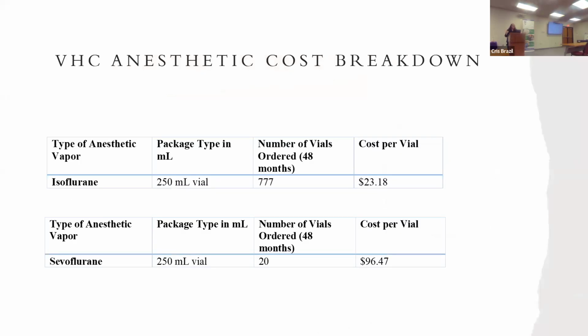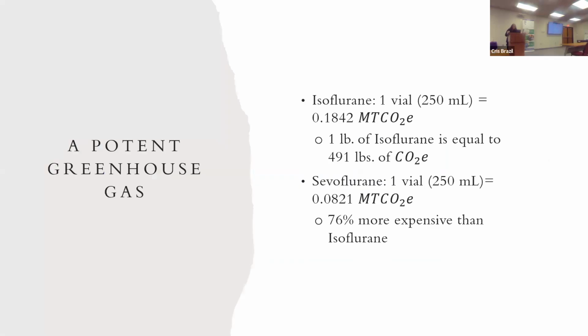So for vet med, we basically use isoflurane and sevoflurane, the two anesthetic vapors primarily used. This is the cost breakdown. So you can see sevoflurane is quite a bit more pricey than isoflurane. And there is a little bit of a difference between the emissions output for these two as well. So they're both potent, but isoflurane is a more potent greenhouse gas. And you can see 1 pound of isoflurane is equal to 491 pounds of CO2 equivalent, where sevoflurane is a little bit less, but it's 76% more expensive. So that's why isoflurane is typically used over sevoflurane, unfortunately.